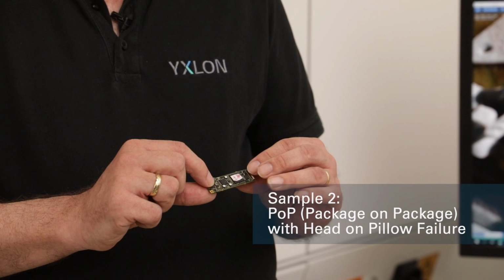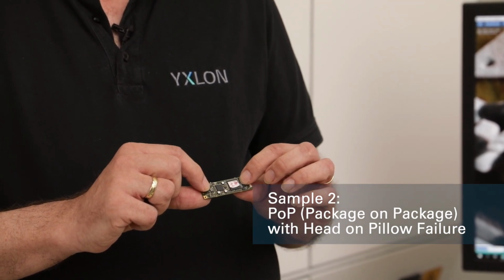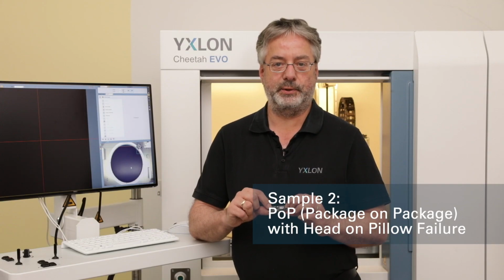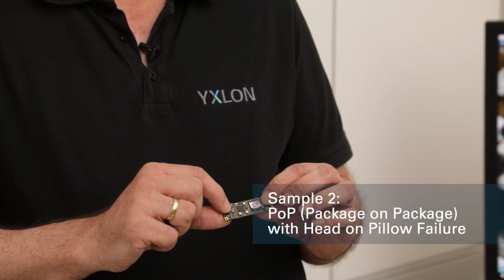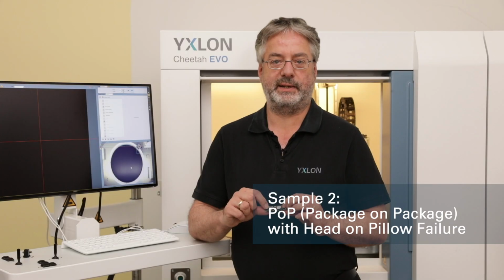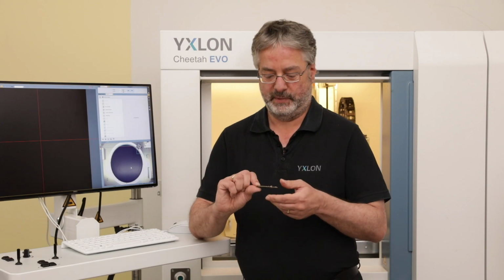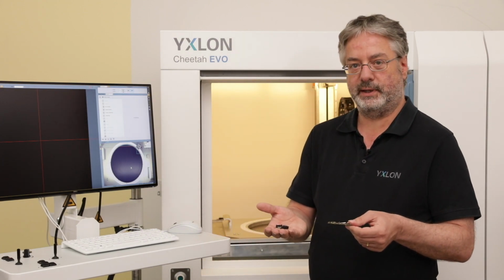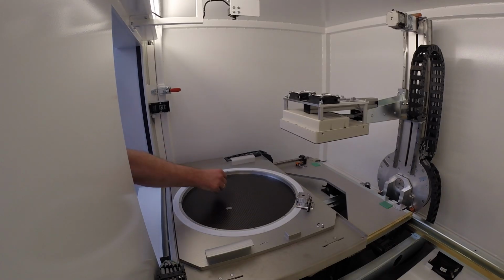The next one is a package on package with a head-on-pillow. This is very difficult to see in 2D, and so we are using CT for detecting the head-on-pillow on this sample here. So I placed these two samples at first into the X-ray system to show you what we are looking for.